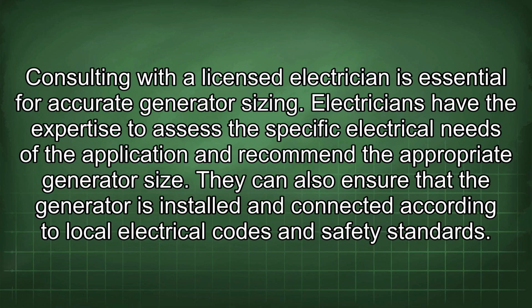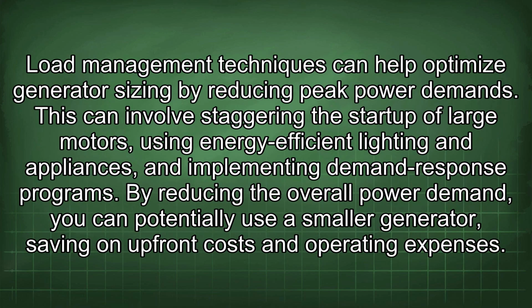Consulting with a licensed electrician is essential for accurate generator sizing. Electricians have the expertise to assess the specific electrical needs of the application and recommend the appropriate generator size. They can also ensure that the generator is installed and connected according to local electrical codes and safety standards. Load management techniques can help optimize generator sizing by reducing peak power demands. This can involve staggering the startup of large motors, using energy-efficient lighting and appliances, and implementing demand response programs. By reducing the overall power demand, you can potentially use a smaller generator, saving on upfront costs and operating expenses.